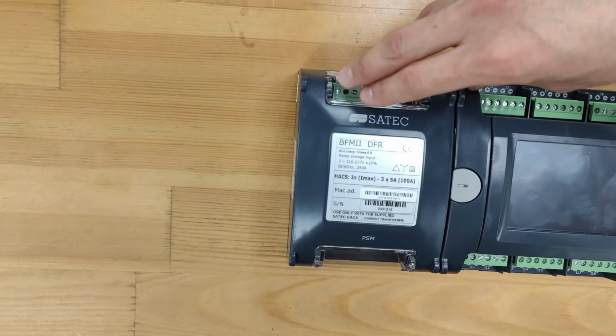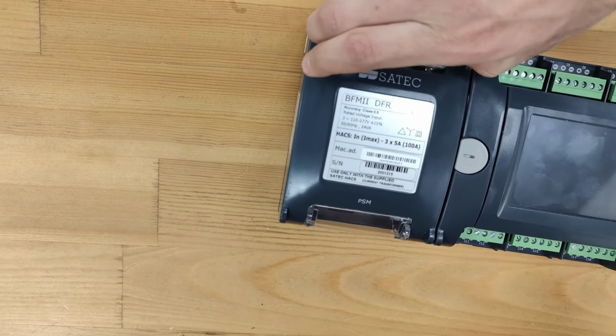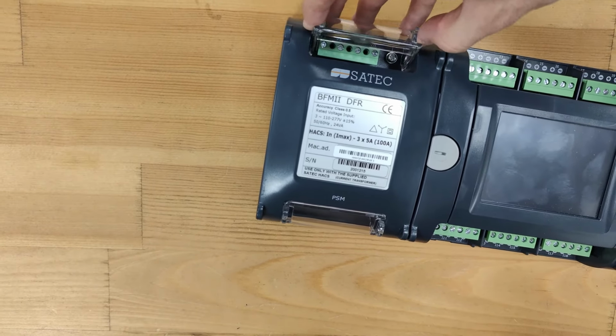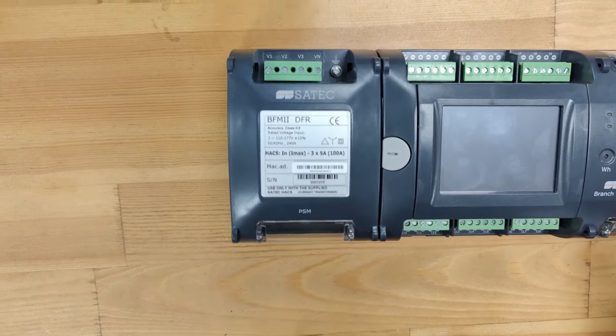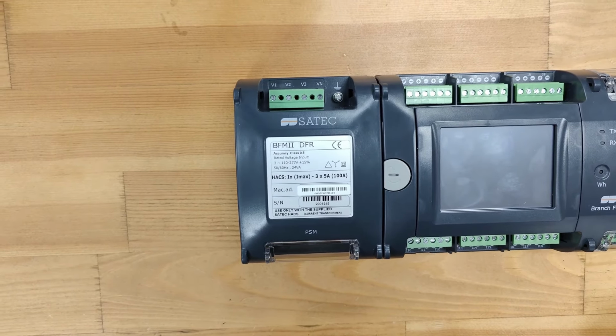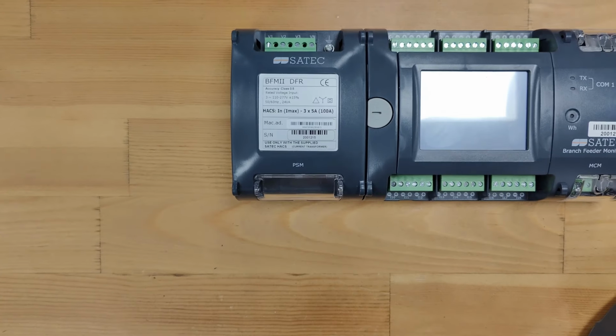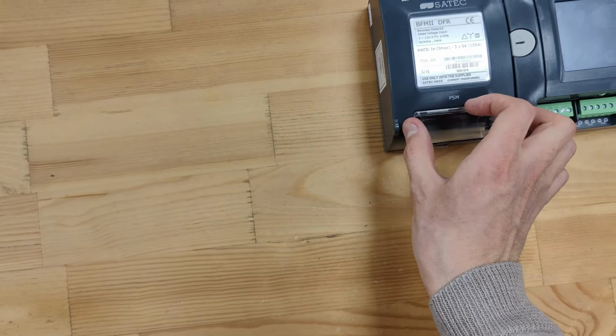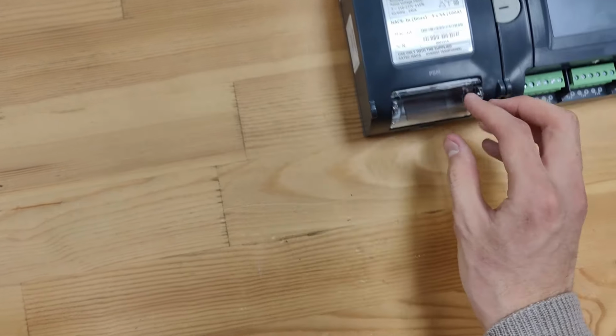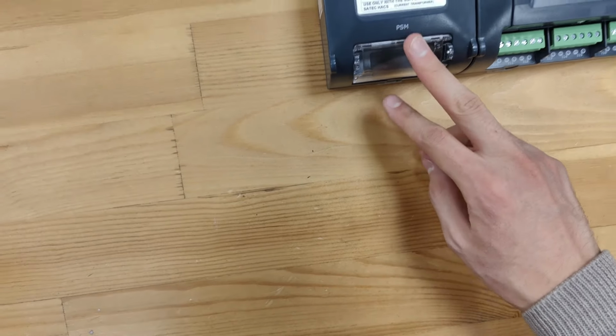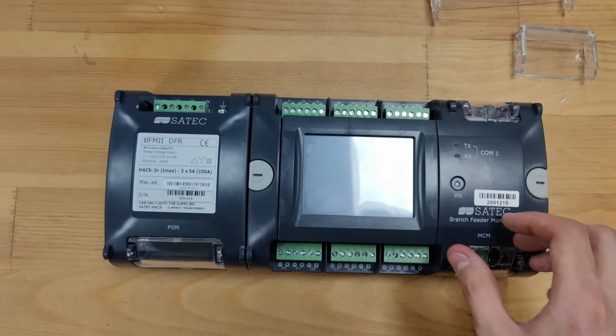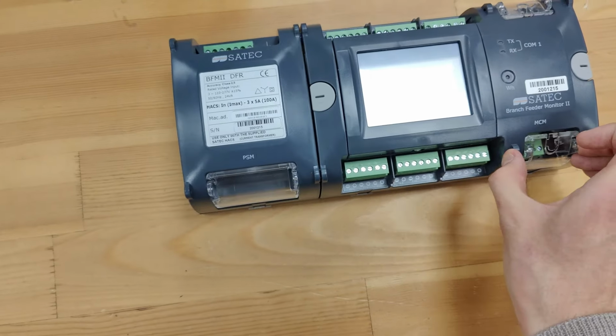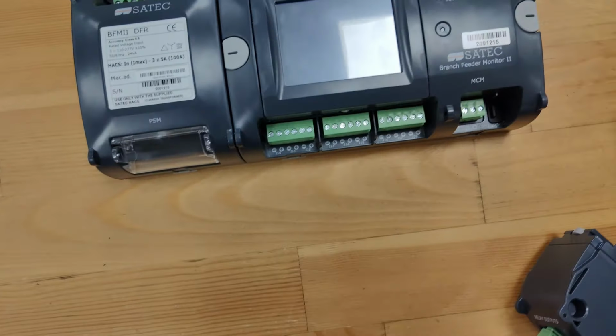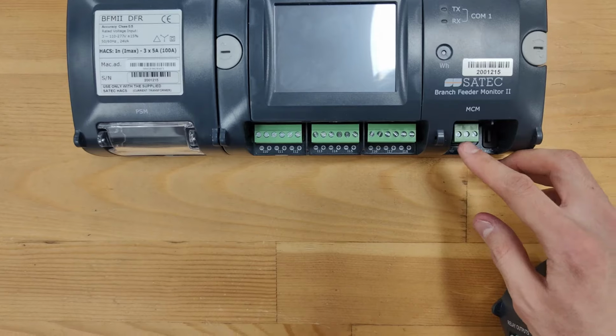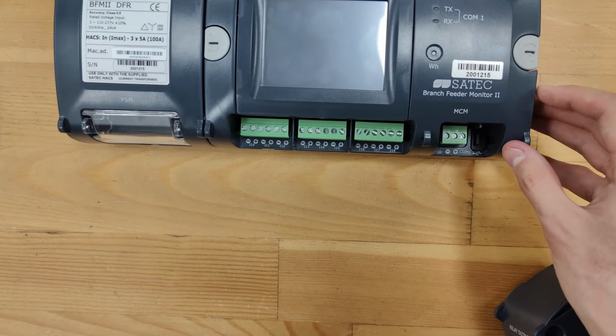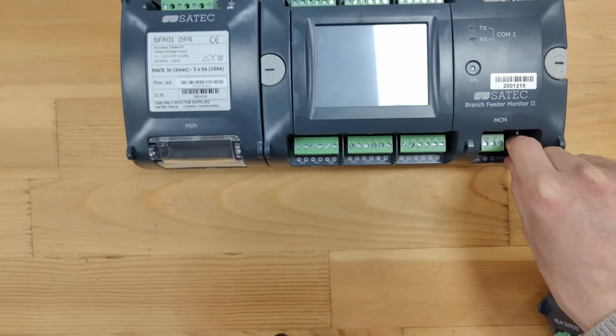Here we can also see the display of the BFM II, and this is where the voltage circuits are connected. The voltage module is a power supply module. Here we can see the PSM abbreviation. The device is powered from the measurement circuits. It's also possible to connect an additional voltage module. This makes it possible to measure the power parameters of several feeders from the one device.